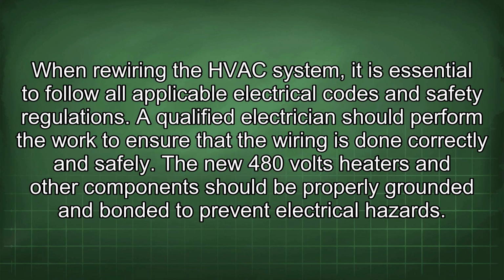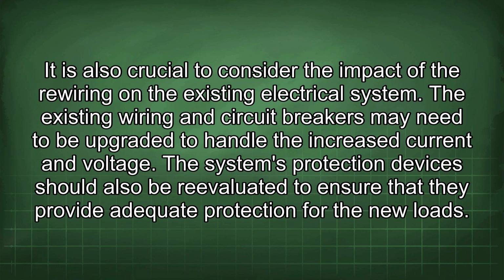When rewiring the HVAC system, it is essential to follow all applicable electrical codes and safety regulations. A qualified electrician should perform the work to ensure that the wiring is done correctly and safely. The new 480 volt heaters and other components should be properly grounded and bonded to prevent electrical hazards. It is also crucial to consider the impact of the rewiring on the existing electrical system. The existing wiring and circuit breakers may need to be upgraded to handle the increased current and voltage. The system's protection devices should also be re-evaluated to ensure that they provide adequate protection for the new loads.